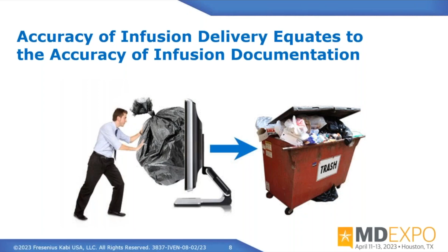What this buys us is the data generated by the infusion pump is going to be more accurate. If the machine delivering the infusion is accurate, the data generated by that machine is going to be accurate and going out to the EMR, going out to dashboards, reporting into biomed, reporting into pharmacy. We're getting more and more connected with our infusion devices and our medical devices, so having accurate data is critical for these systems.